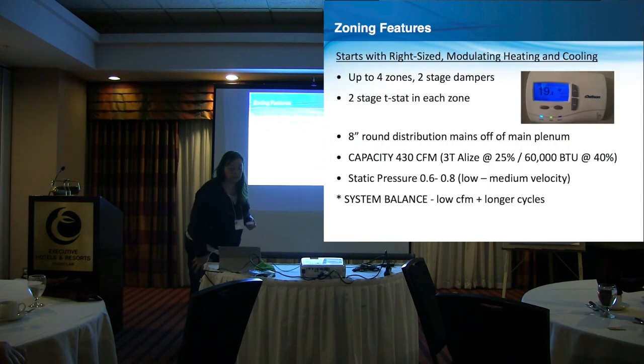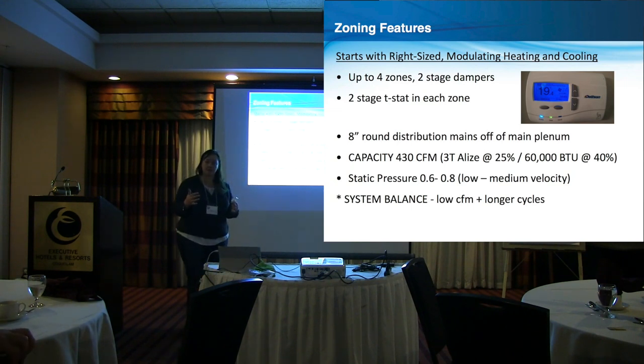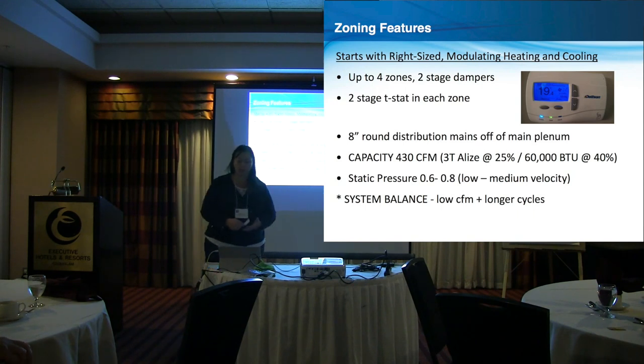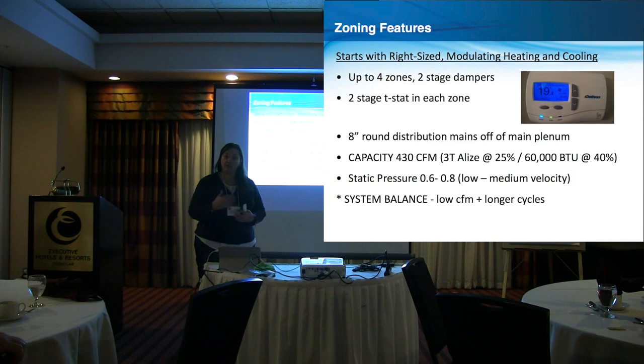So our zoning system, just to walk through it really quick, uses two-stage dampers. Instead of two zones fighting each other, like the top floor in a townhouse calling for high cooling in the summer and the basement calling for high heat, those two zones are going to open up and share amongst themselves. So you're really optimizing the energy that's already in the house. It's a very cool system. The capacity maxes out at 60,000 BTU and 3 tons of cooling. And again, with that modulation and the smart ducts, we're really able to play, and with that system you can still stay with traditional ducts, traditional round.